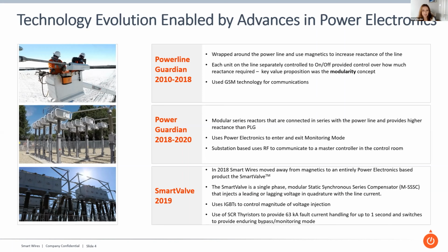So they only had the capacity to increase. They were like distributed series reactors or big inductors, and they were pushing power off the lines to which they were connected. If you look at the middle picture there, that's an installation in UKPN, where installing this equipment on the, I think it was the 132 kV grid, got about an additional 100 megawatts of transfer capacity across 3 circuits by balancing them out. But we did start to hit limitations in terms of scale of application when we were using magnetics, and of course in terms of cost as well.